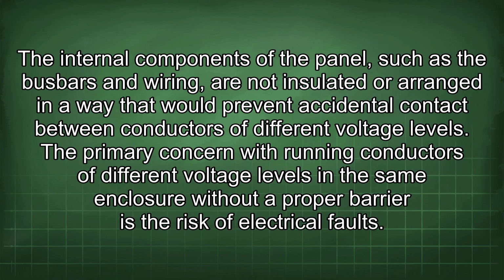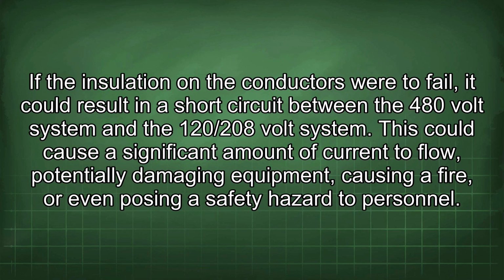The primary concern with running conductors of different voltage levels in the same enclosure without a proper barrier is the risk of electrical faults. If the insulation on the conductors were to fail, it could result in a short circuit between the 480 volt system and the 120/208 volt system. This could cause a significant amount of current to flow, potentially damaging equipment, causing a fire, or even posing a safety hazard to personnel.